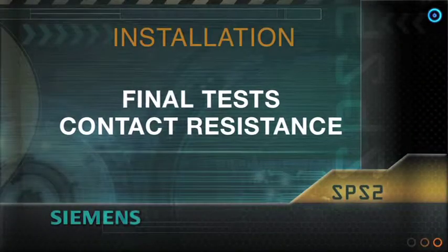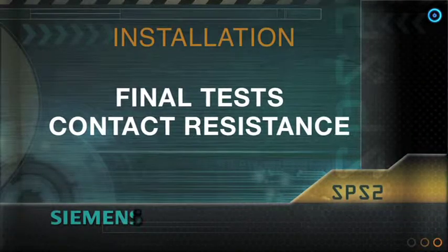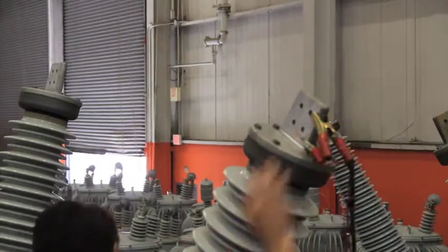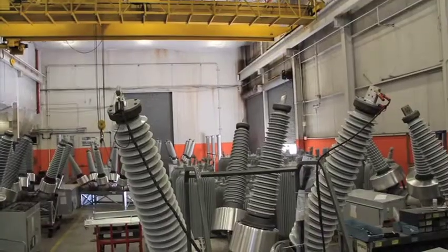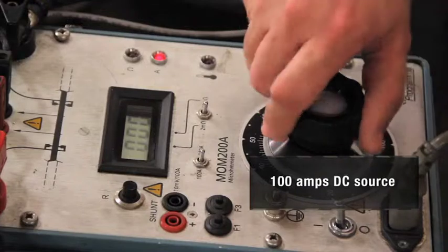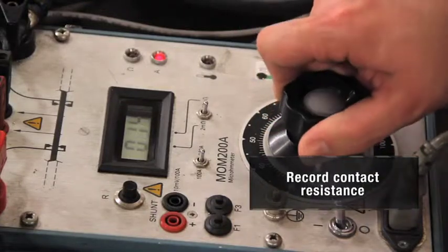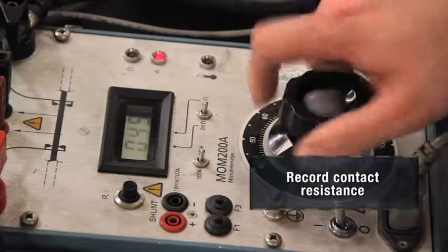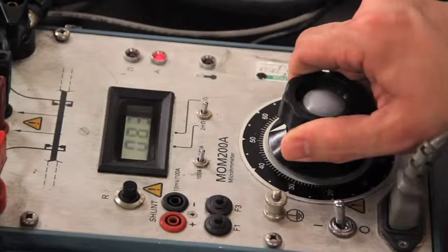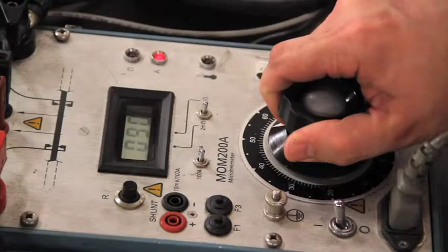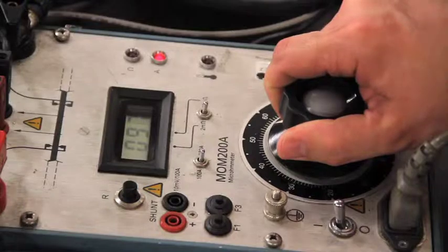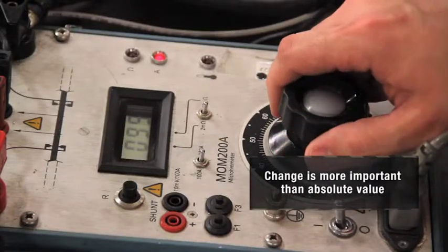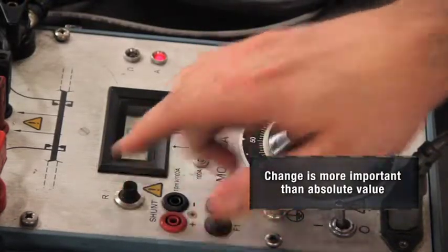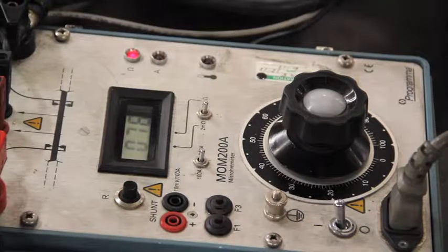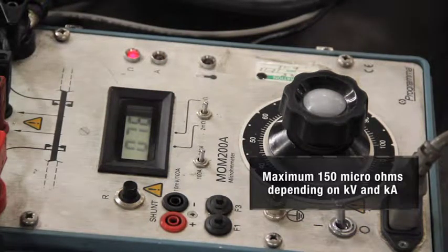Installation. Final tests, contact resistance. Measure the contact resistance terminal to terminal with a testing device of 100 amps DC source. Record the contact resistance of each pole to provide a permanent baseline reference against which future measurements can be compared. In diagnosing impending problems, the change in contact resistance over time is far more significant than the absolute value of the resistance. Maximum values for new contacts are 150 microohms.